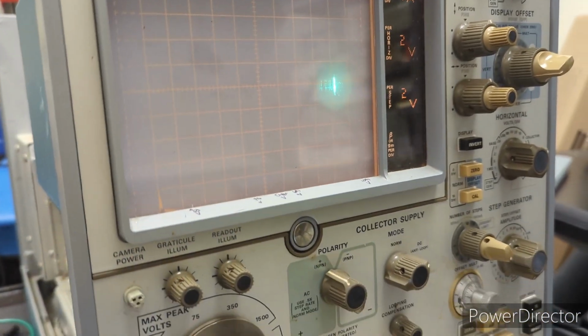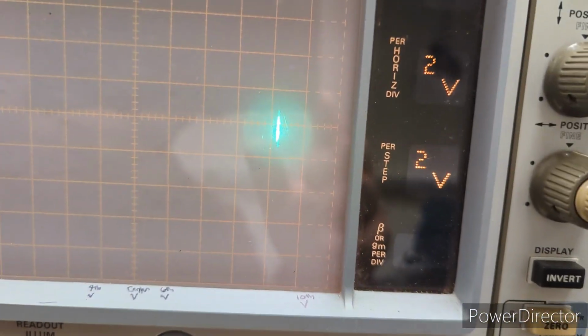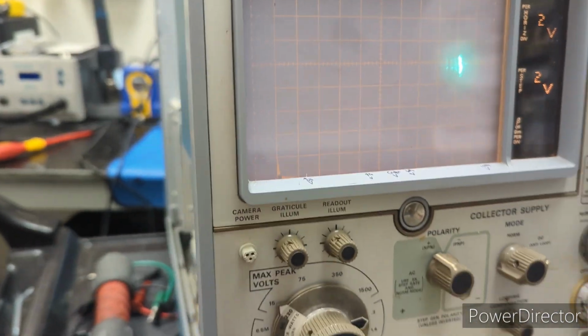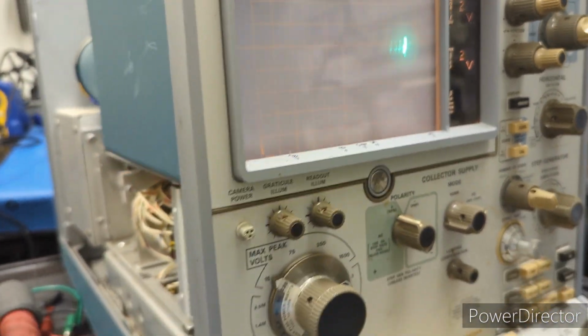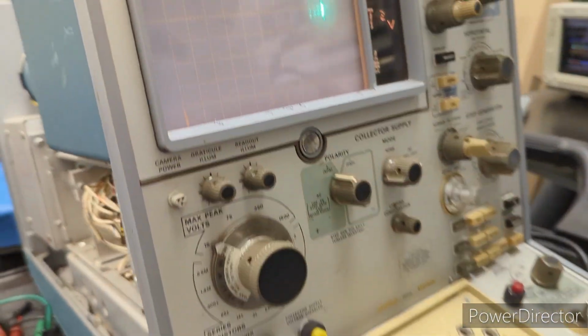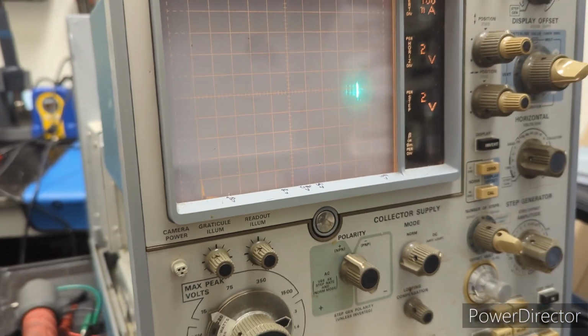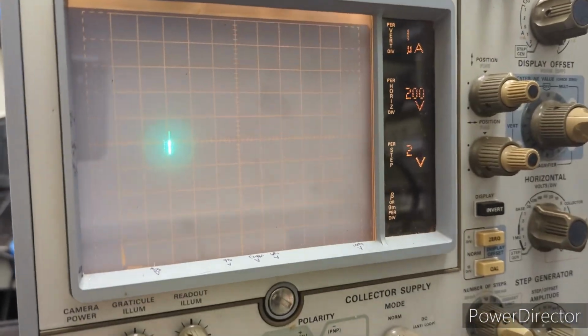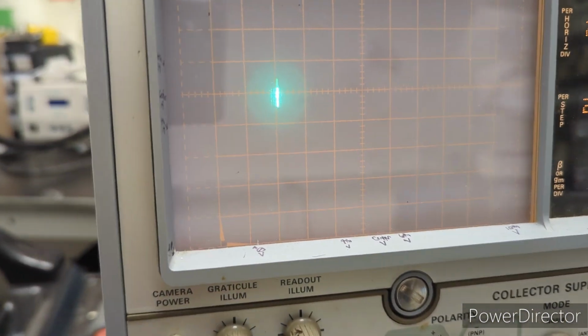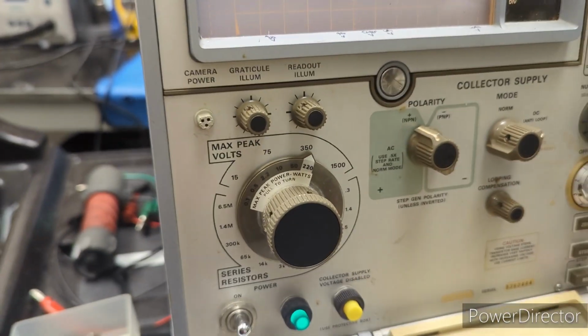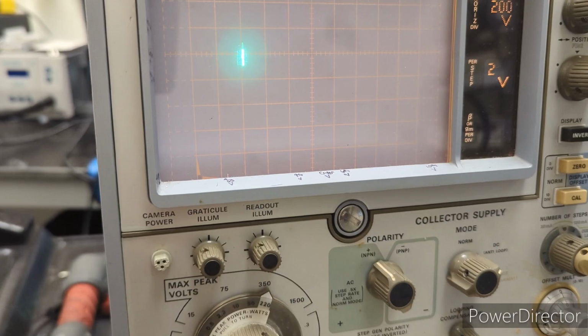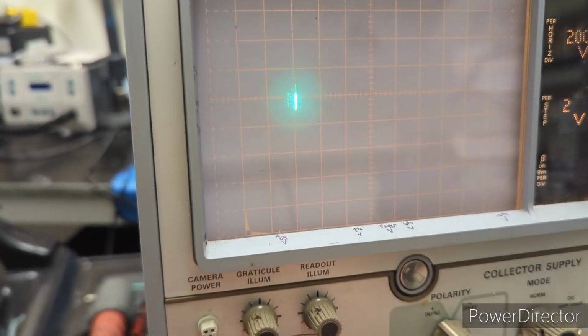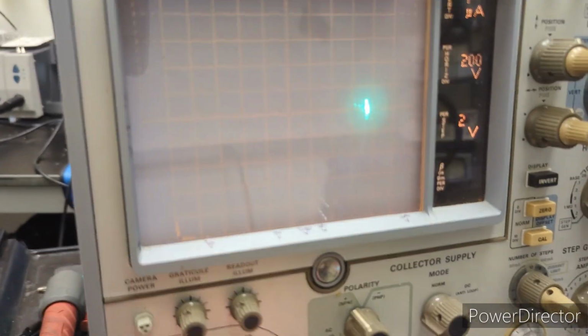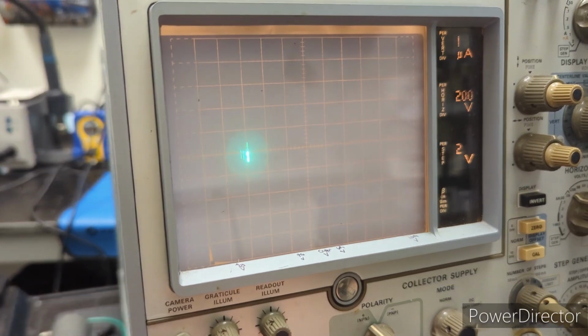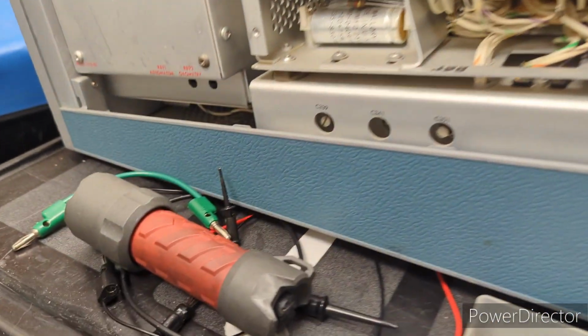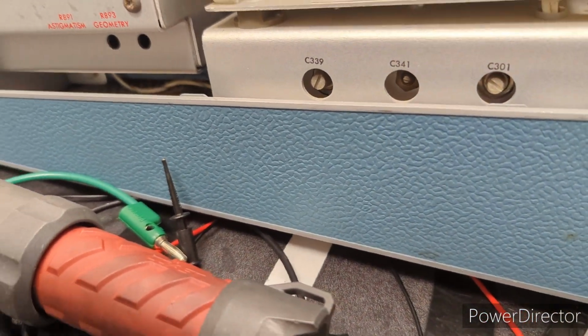I feel like while watching Zen's video, he was able to get it much shorter. So there might be something else going on here with the instrument that needs to be fixed. But we'll see how the rest of the calibration goes. Okay, and now it's asking you to make pretty much the same adjustment, except now we've had the max peak volts knob set to 350 and 1500. I just got done making that adjustment. This is the best I could get it for both settings, and instead of C301, you're adjusting C339.